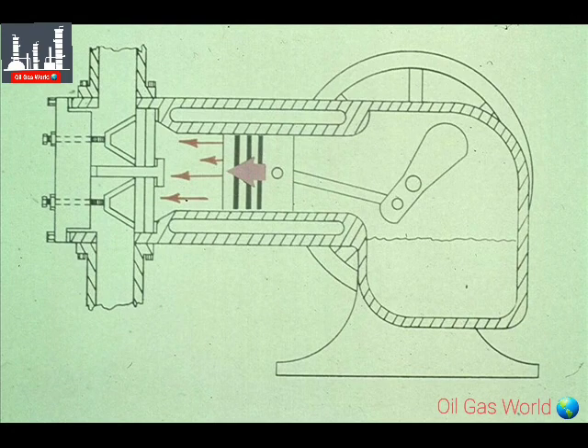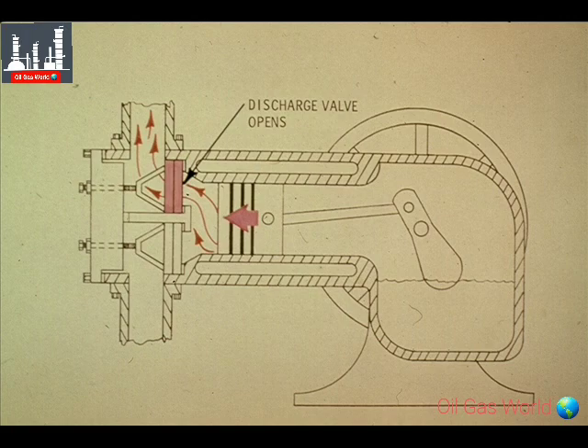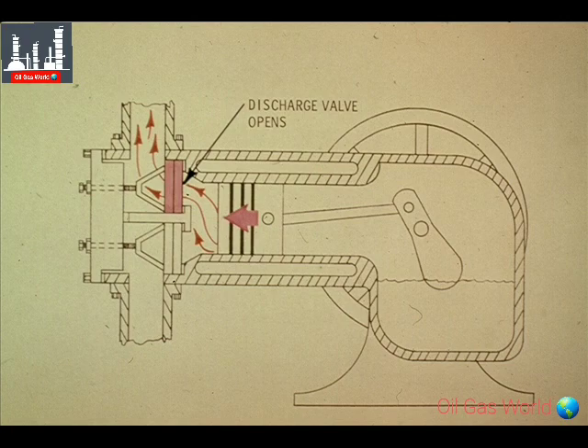The shaft continues to turn, now forcing the piston forward on the compression stroke. The pressure is built up inside the cylinder until it forces the discharge valve to open, and the compressed air, or gas, is forced into the discharge line. This continues until the piston reaches the starting position.